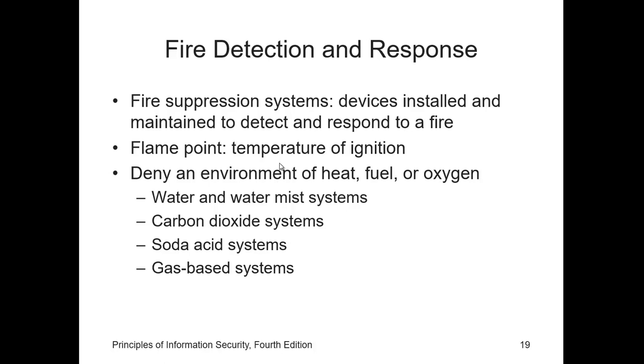Fire suppression systems are devices installed and maintained to detect and respond to a fire, potential fire or combustion situation. These devices typically work to deny an environment of one of the three requirements for fire to burn: temperature, fuel and oxygen. Water and water mist systems reduce the temperature of the flame to extinguish the fire and to saturate some categories of fuels to prevent ignition. Carbon dioxide systems rob fire of its oxygen. The soda acid systems deny fire its fuel by preventing spreading. The gas-based systems disrupt the fire's chemical reaction but leave enough oxygen for people to survive for a short time.